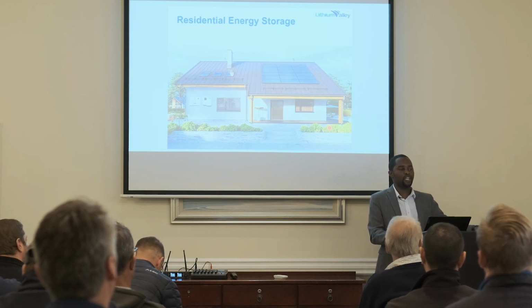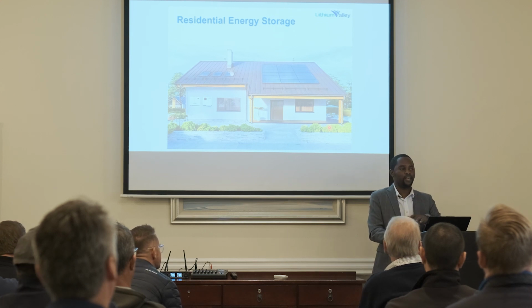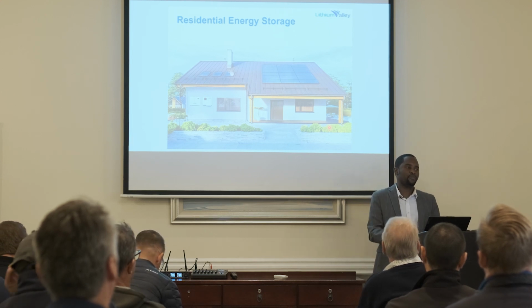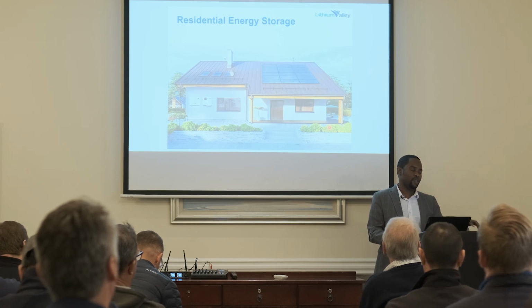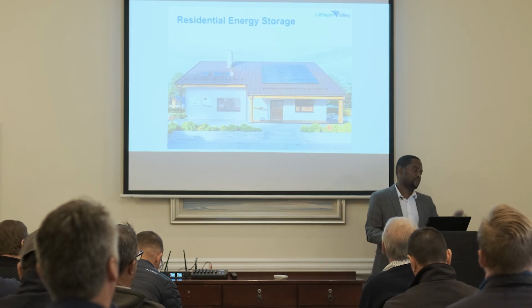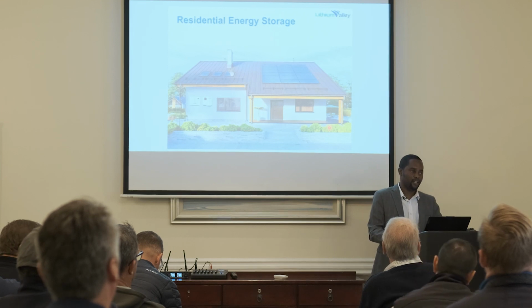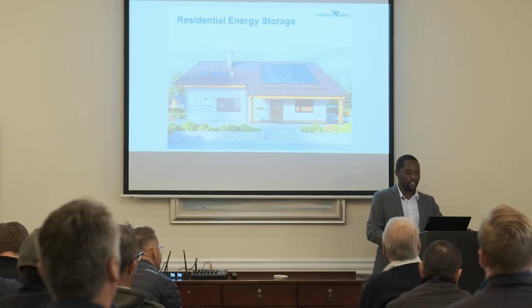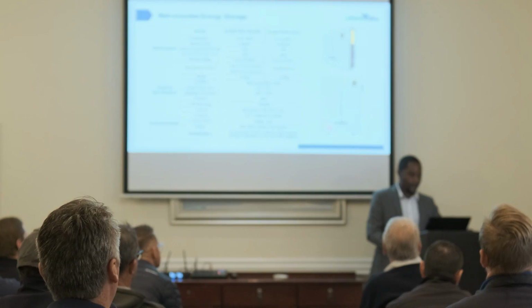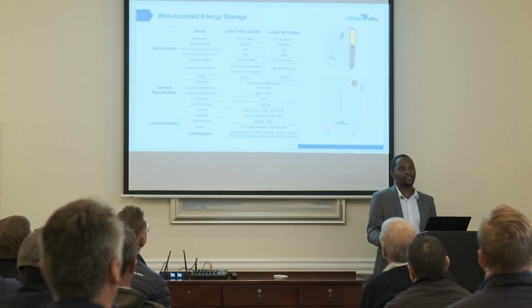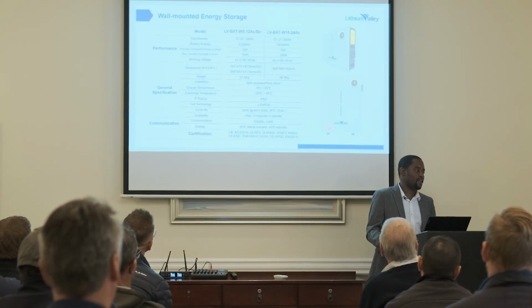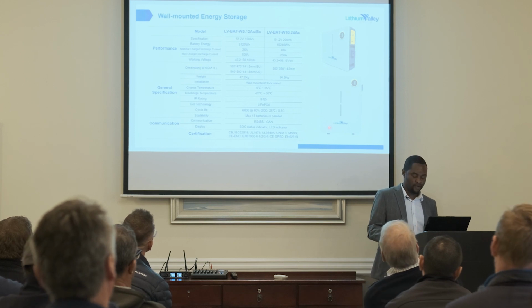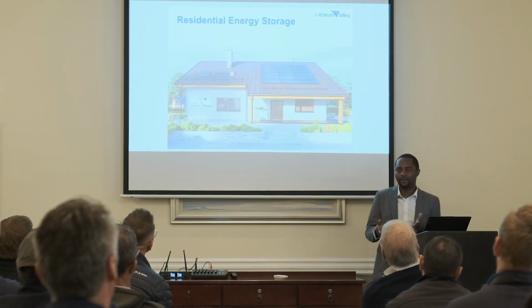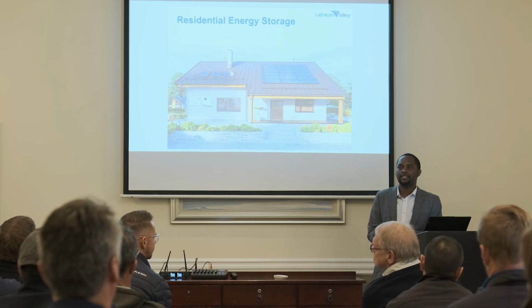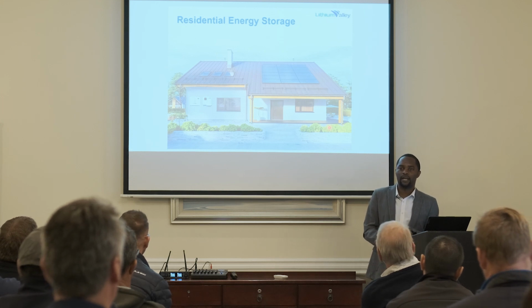With all this, you can have a common battery bank. Each inverter is tapping from the common battery bank through a fuse disconnector. It's important to have a fuse between the battery bus bar and each inverter to protect the inverter. While you are still on that, we've said this is our battery of choice that you can pair with the INVT. Maybe while you are on the inverters, any question on the inverters before we look at the batteries, so that we cover them as they come?